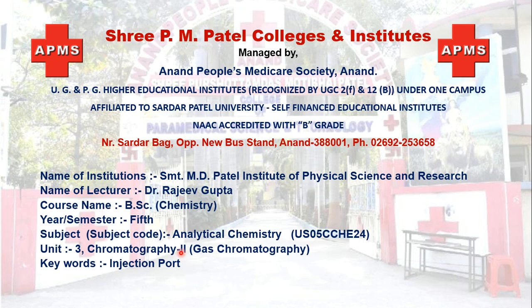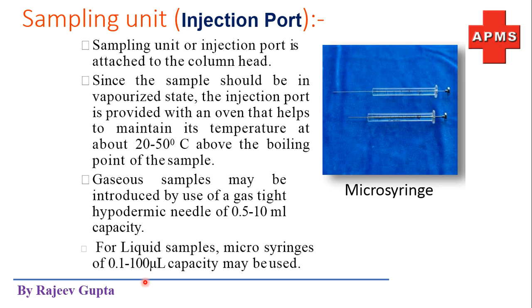In this lecture, I am going to talk about injection ports, which are used to inject our known or unknown sample into the GC instrument. The sampling unit or injection port is attached to the column head — just ahead of the column — where the actual separation of components starts. At this starting point, the injection port is attached, and we inject our sample using syringes.